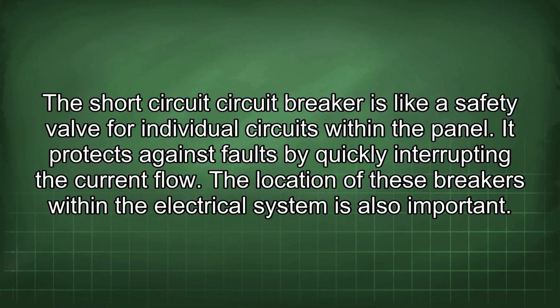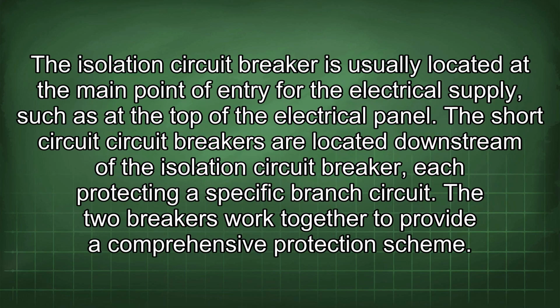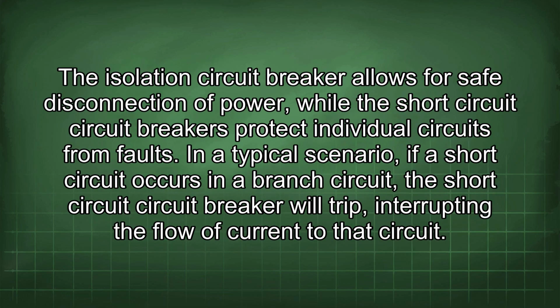The location of these breakers within the electrical system is also important. The isolation circuit breaker is usually located at the main point of entry for the electrical supply, such as at the top of the electrical panel. The short-circuit circuit breakers are located downstream of the isolation circuit breaker, each protecting a specific branch circuit. The two breakers work together to provide a comprehensive protection scheme. The isolation circuit breaker allows for safe disconnection of power, while the short-circuit circuit breakers protect individual circuits from faults.